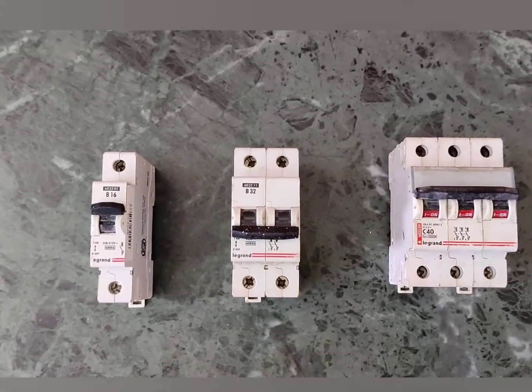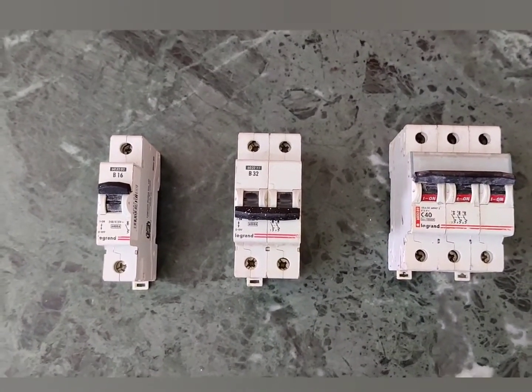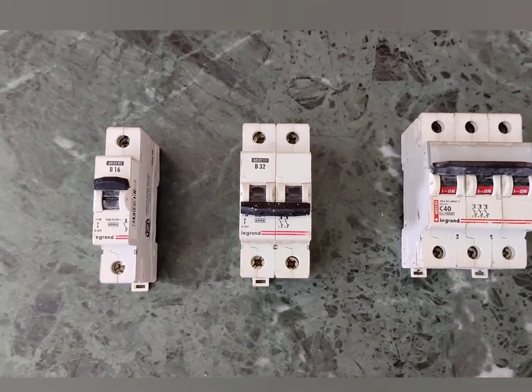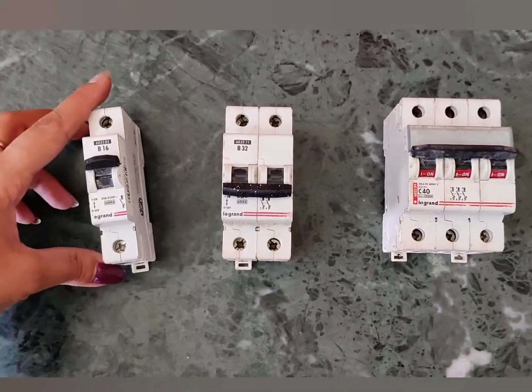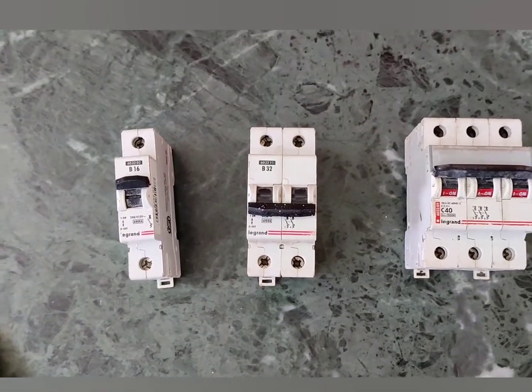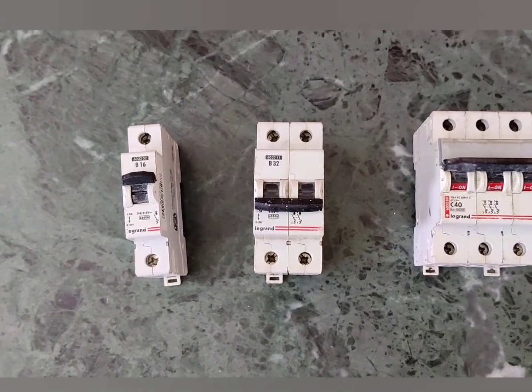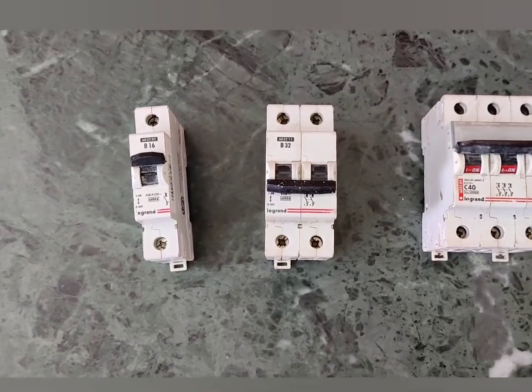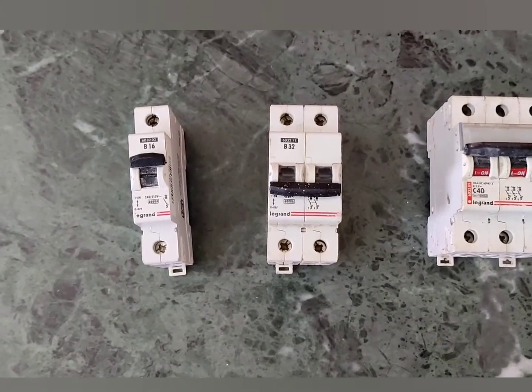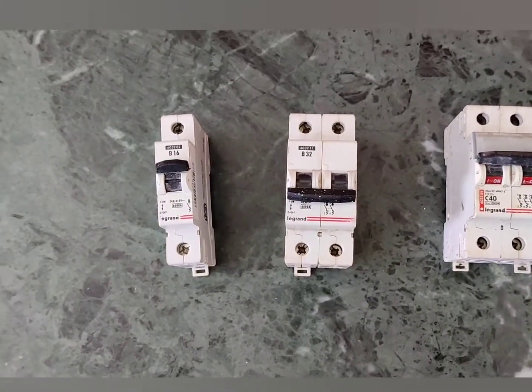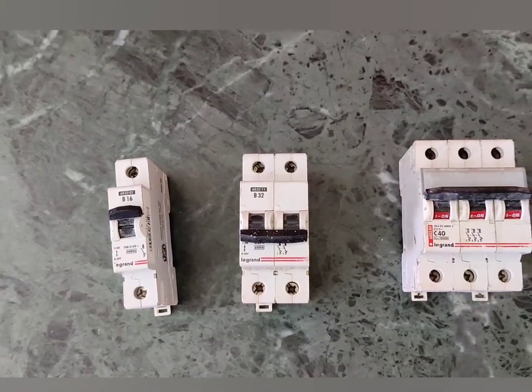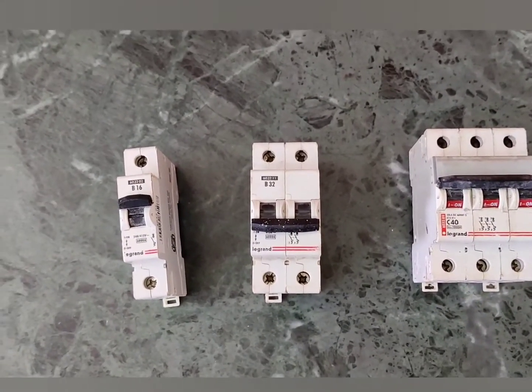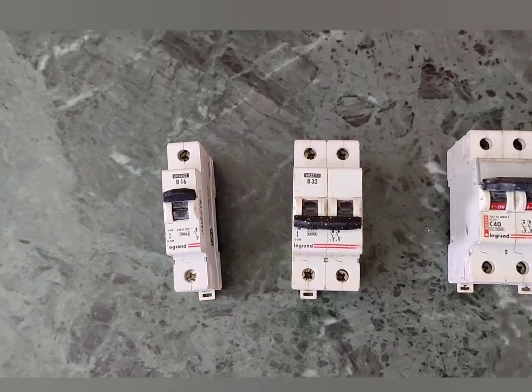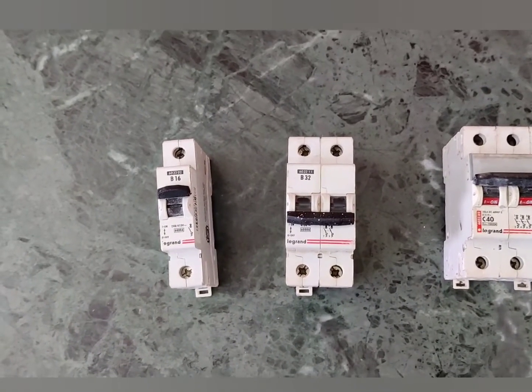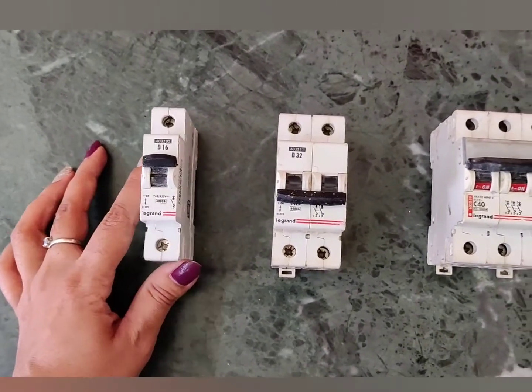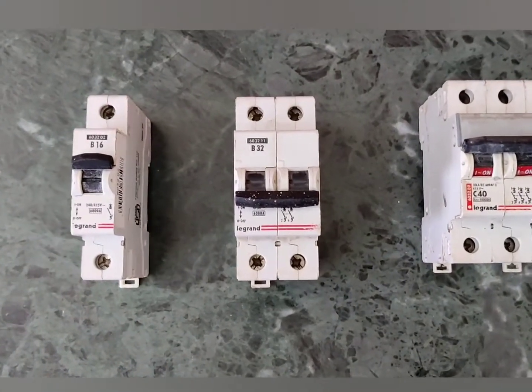The next protective device that we are discussing is known as the MCB, which stands for the miniature circuit breaker. So basically fuses have a few disadvantages, that the fusing element needs to be replaced after every operation, because when a fault occurs, for example a short circuit occurs, the fuse element may melt, so we have to replace it. To avoid that manual effort of replacing the fuse element and to save time, we make use of automatic devices known as circuit breakers.